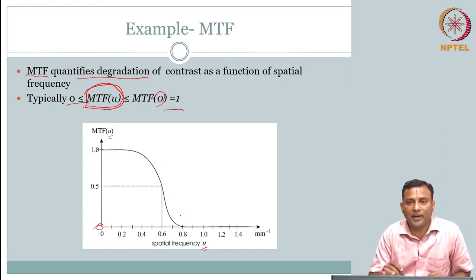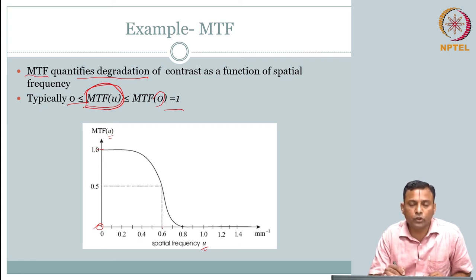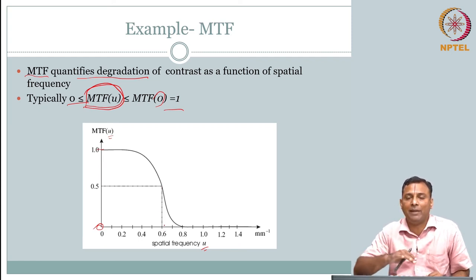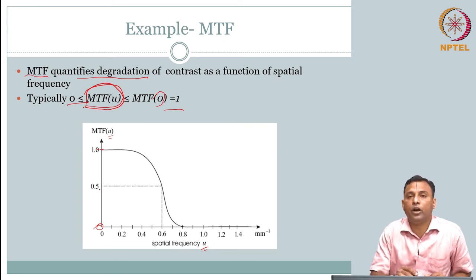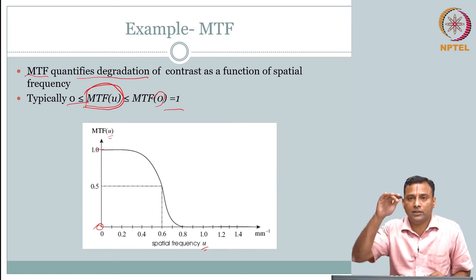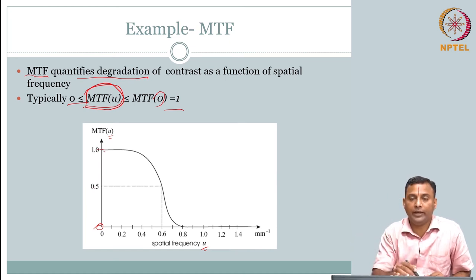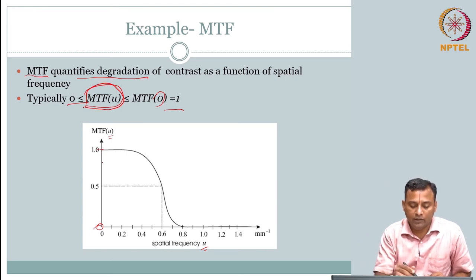We can present the same input to three different system configurations and observe the output. The effect is a decrease in contrast — you can qualitatively say this is better quality than that, and the third is the poorest. The fluctuation between white and black is captured for all frequencies. When higher frequency content is reduced, the image starts to look blurry — something we also saw with the head scan. There is a relationship between resolution and contrast, which you can appreciate using MTF: if the MTF falls off, image quality — contrast — degrades.